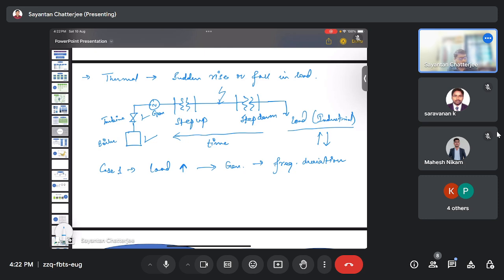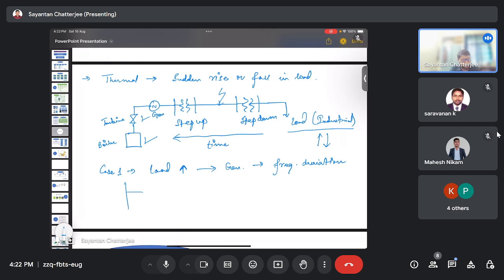So right now, as frequency rises and falls, say it's operating at F1, but based on that there would be a sudden change observed, and after that AGC, automatic generation control, comes into play. Have you heard the term automatic generation control? So the frequency would drop down to some point, and there would be a disturbance pattern. After that, with AGC, these things would return back to the normal operating frequency, because by that time the generation would try to increase, the boiler rate would also increase, and the governor action will take place.